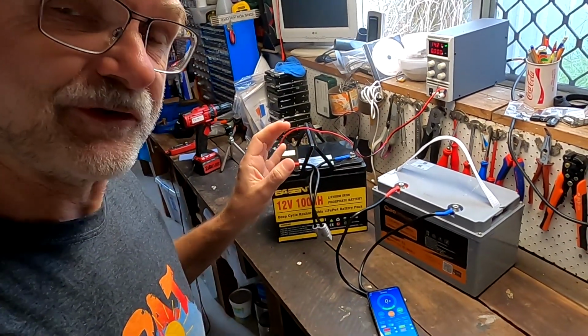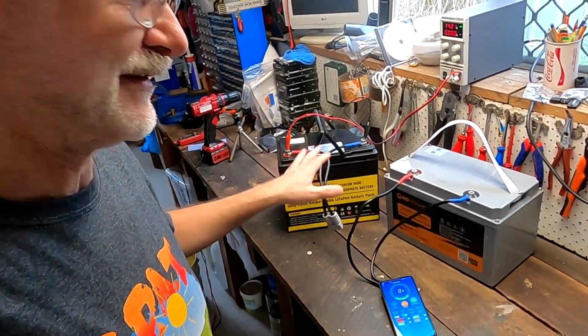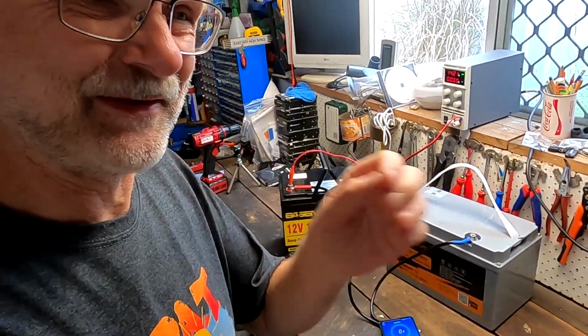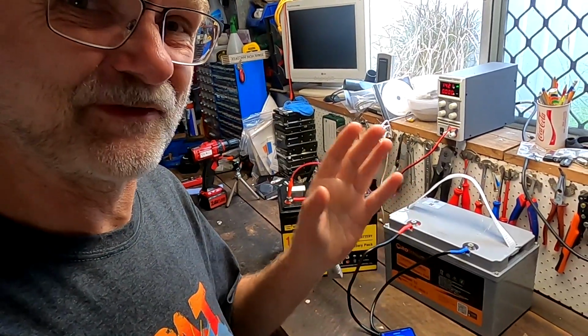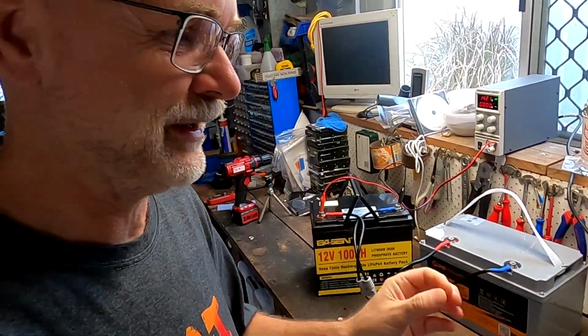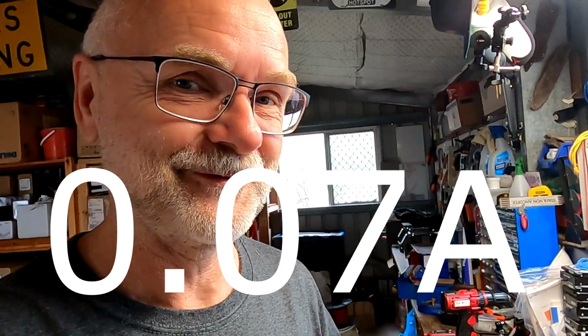Both batteries have a similar JK-BMS inside, and these JK-BMSs have a balance current of about 70 to 80 milliamps only. That's 0.07 amps, for a 100 ampere hour battery.